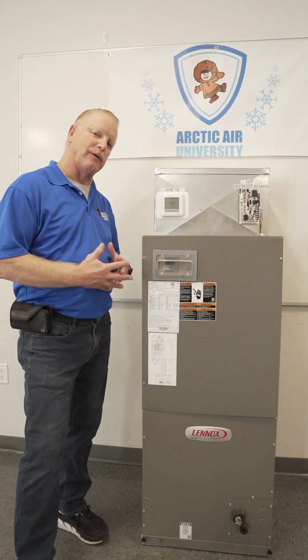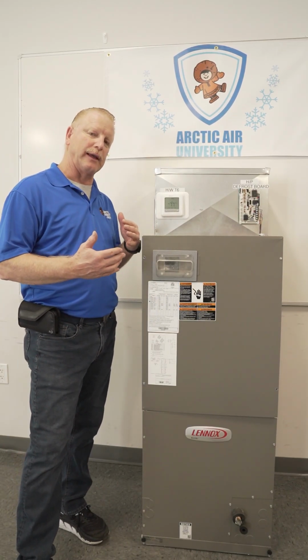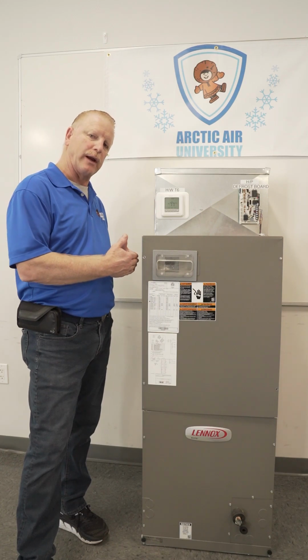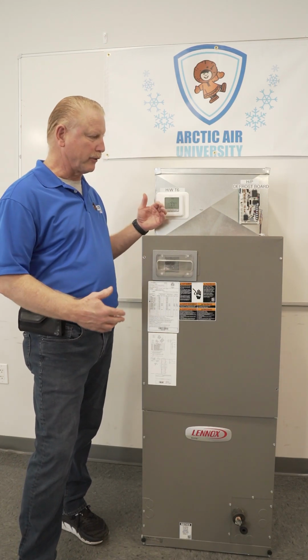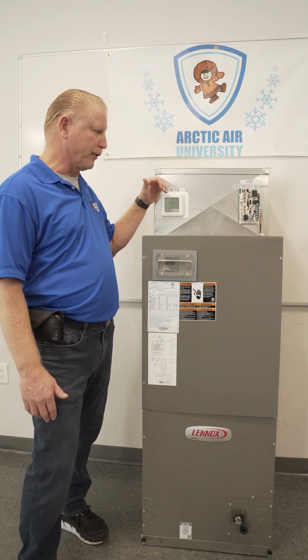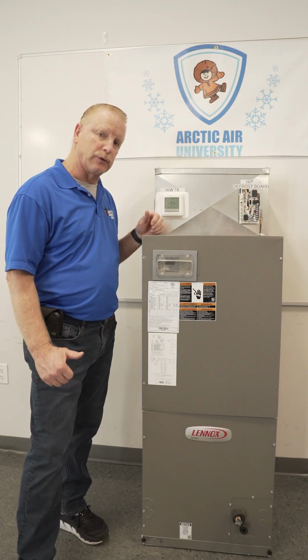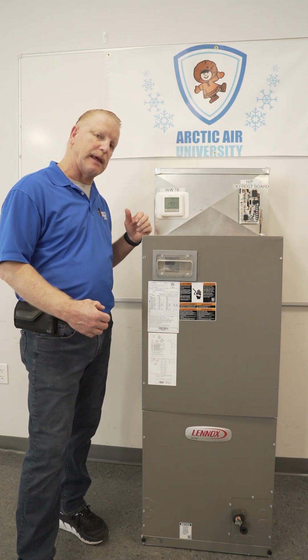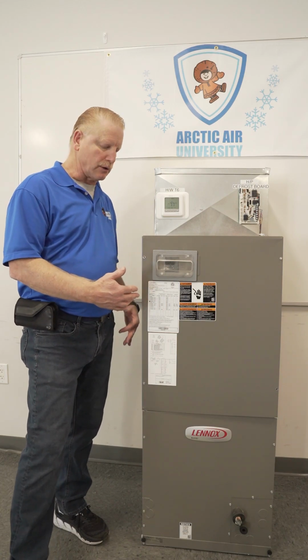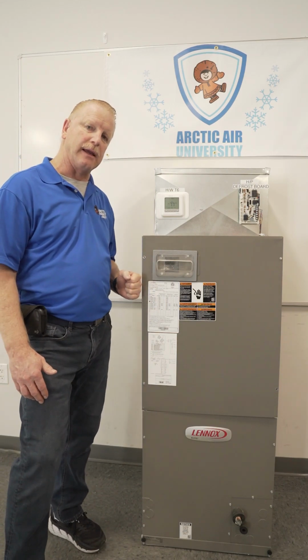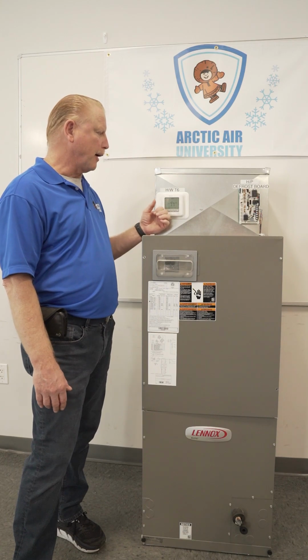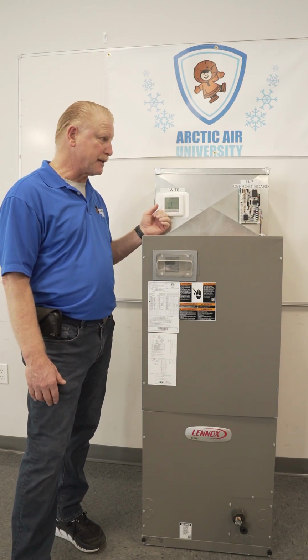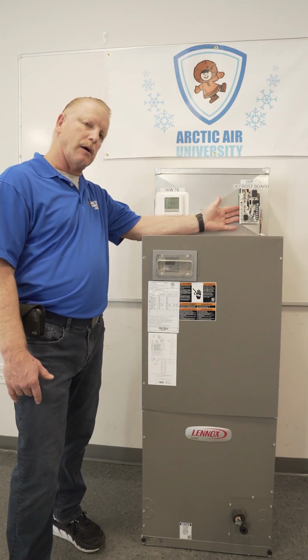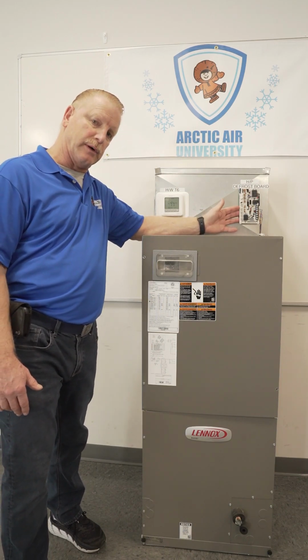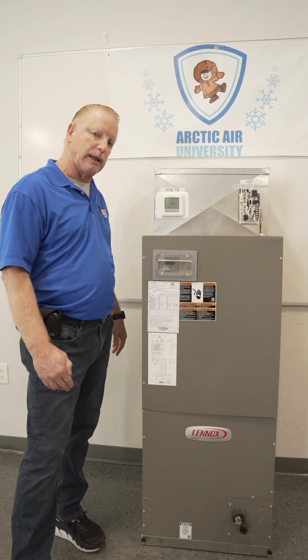Everyone. Today we're going to be going over installing electric strip heaters for a heat pump application. Also going over the low voltage wiring both in the thermostat and in the outdoor defrost board. For today, our demonstration units are going to be one of our Lennox CBA 27s, our Honeywell T6 thermostat, along with a basic heat pump defrost board. This one happens to be out of one of our Lennox units.